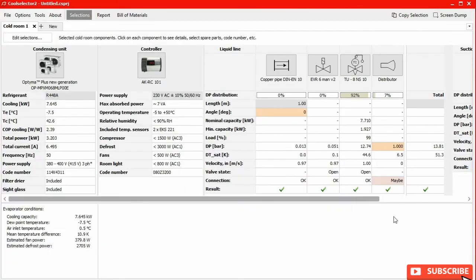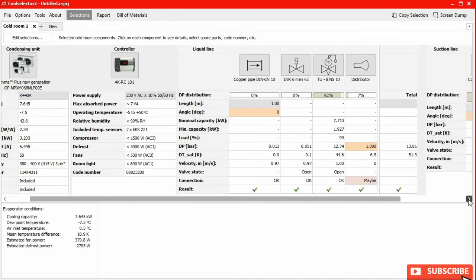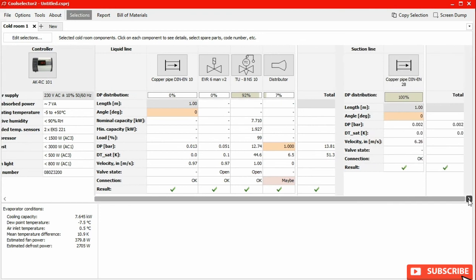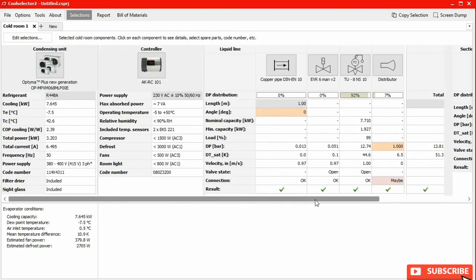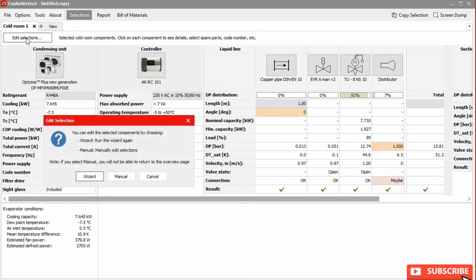The application will now display all the suggested components for the cold room. The condensing unit is selected based on your required cooling capacity. All other components will be sized and selected based on the condensing unit found, as well as the requirements for the cold room. Danfoss doesn't provide any evaporators. However, the application does calculate all the required values, which can be provided to an external supplier for selection of the evaporator. If you need to go back and adjust the calculation, you can do so by selecting the Edit Selections button at the top left.